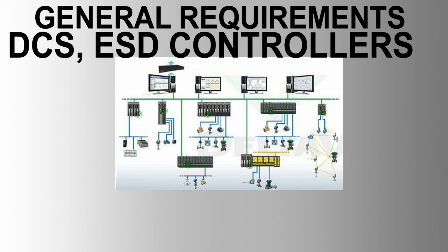Vendor coordination. Work closely with equipment vendors to ensure compatibility and proper integration of ESD systems with packaged equipment. Ensure that vendor-supplied equipment meets the necessary safety and performance standards for integration with the ESD system. Interfaces with other electrical equipment systems shall be via volt-free contacts on interposing relays.